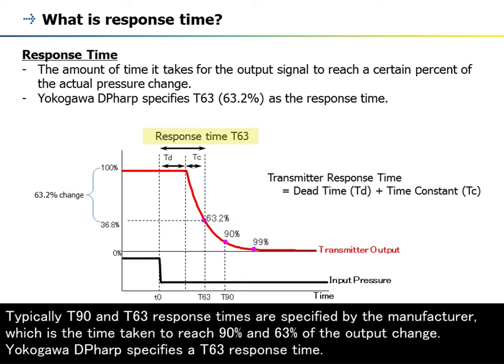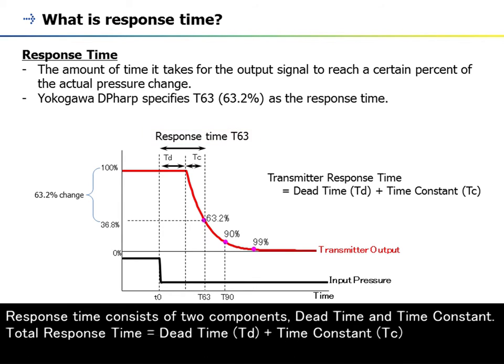Yokogawa DP-HARP specifies a T63 response time. Response time consists of two components: dead time and time constant. Total response time equals dead time, Td, plus time constant, Tc.